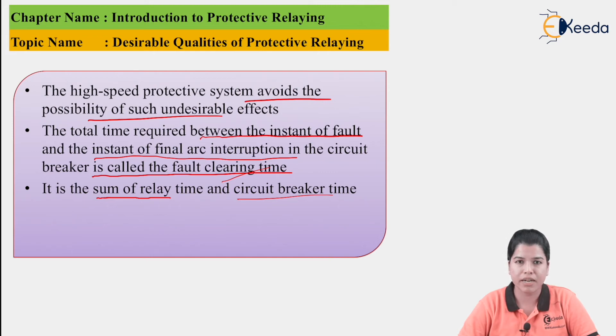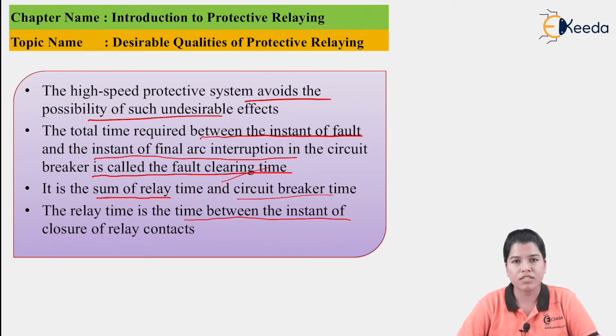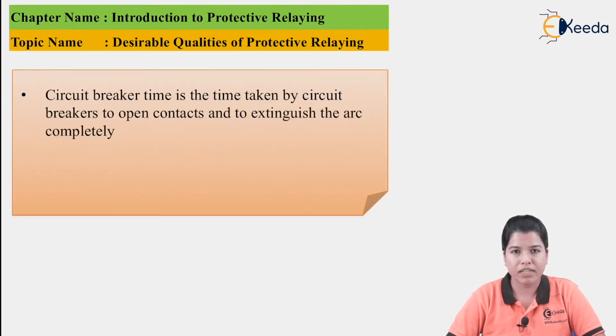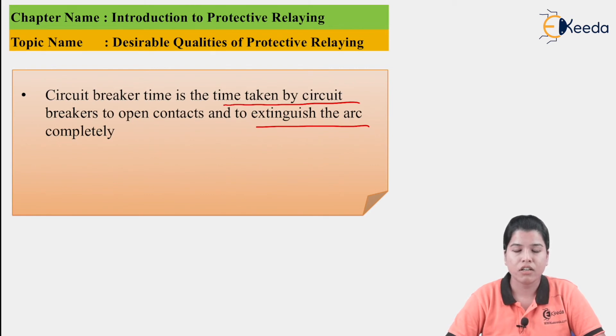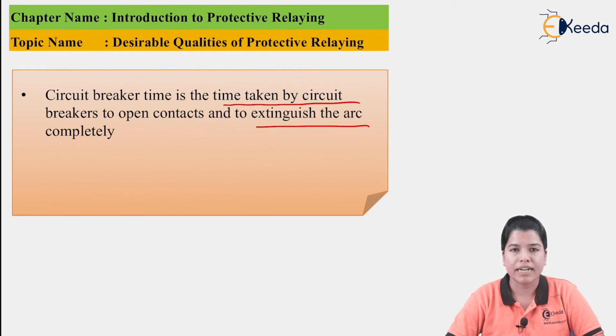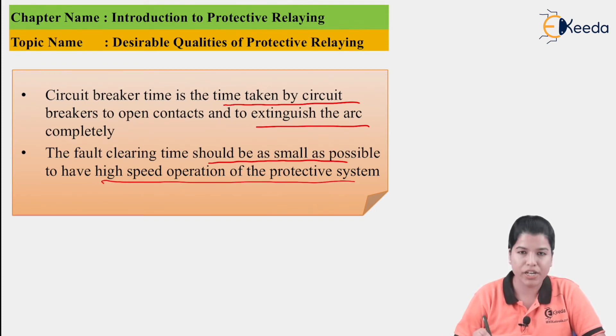Relay time is the time between the instant of closure of the relay contacts. Under normal operating conditions the relay contacts are open; when a fault occurs the relay contacts close. Circuit breaker time is the time taken by the circuit breaker to open its contacts and extinguish the arc completely. Under normal operating conditions the circuit breaker contacts are closed; when the relay sends a signal, the contacts should open. The fault clearing time should be as small as possible to achieve high speed of operation.